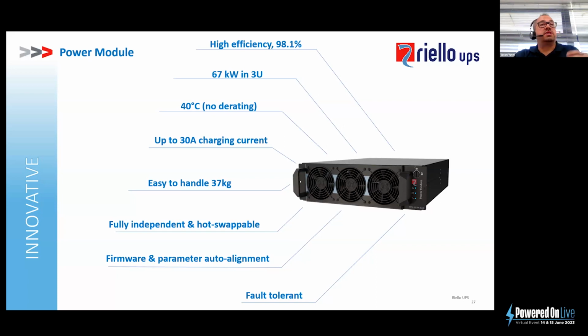So again, this power module, obviously, it's very compact. It's highly efficient. It's 67 kilowatts in 3U. It can operate up to 40 degrees C. So again, the operational rooms can be run at high temperatures, with less cooling required. It can charge batteries up to a high current. Easy to handle at only 37 kgs. Fully independent, hot swappable, fully isolated from all the other modules. So again, reduced fault propagation. And it has full firmware and parameter auto alignment. So it's very easy to use, and that's one of the benefits of this system.